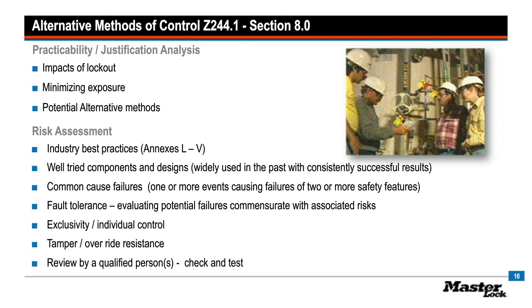We look at exclusivity. How do we provide individual control, person by person, who may be participating in alternative methods? It is not enough to do an alternative method to protect one person if we know the job may require two or more. That loss of sight of who else may be involved in the job can result in the person originating the alternative method removing the protections and exposing people. So the number of people involved and how they each participate in that alternative method is crucial.